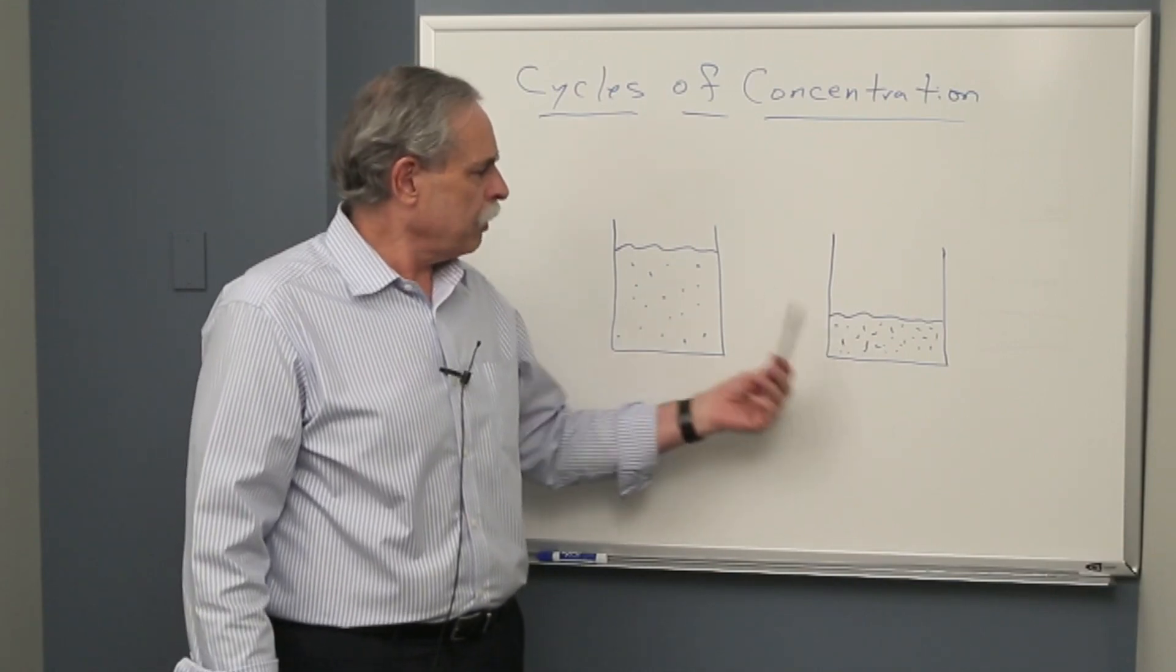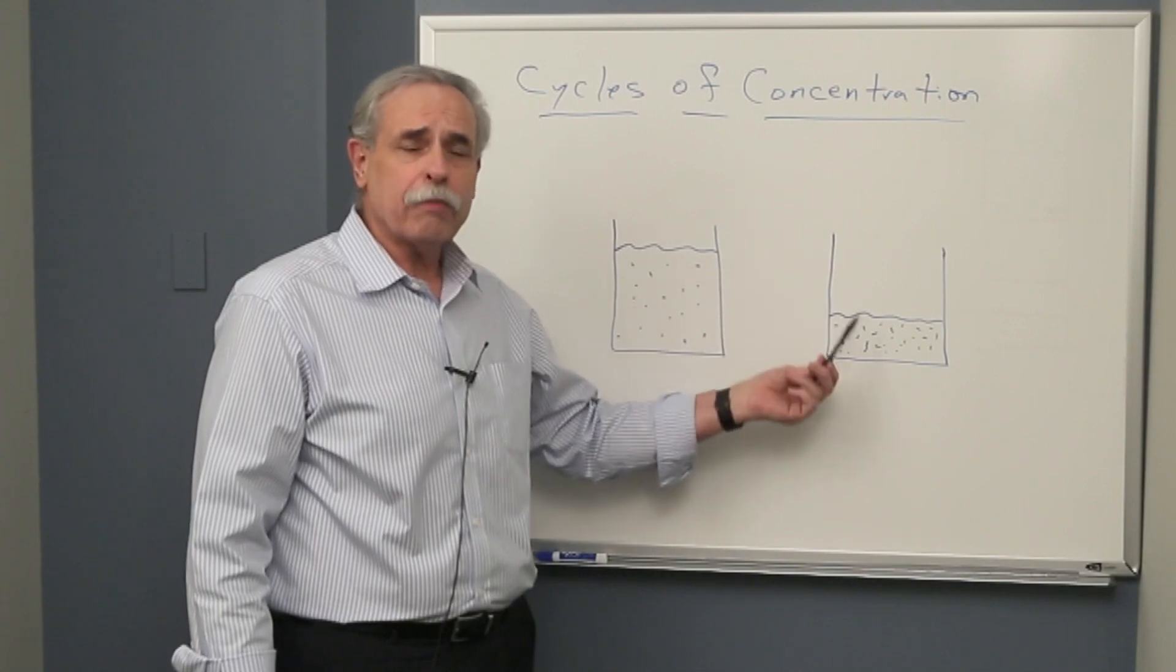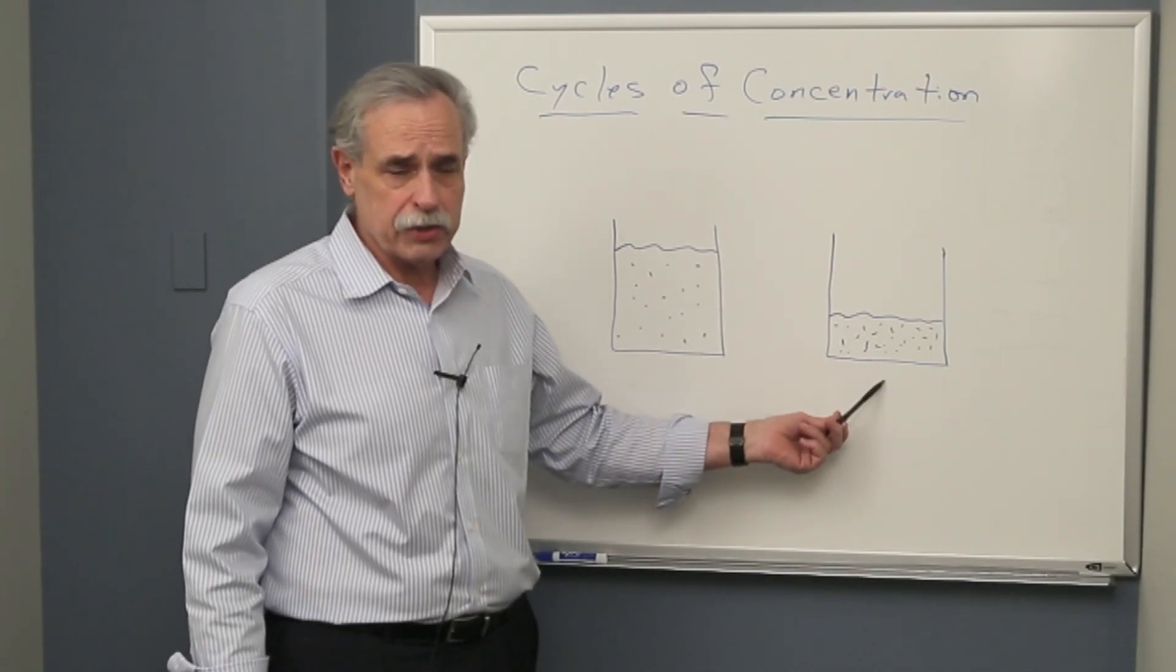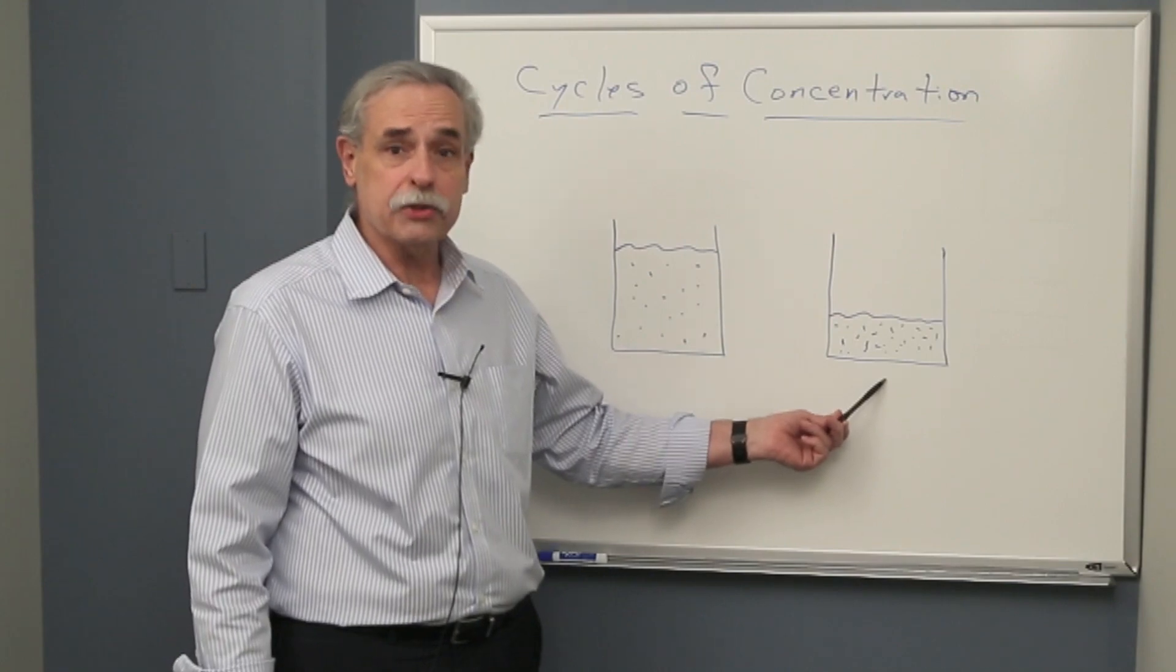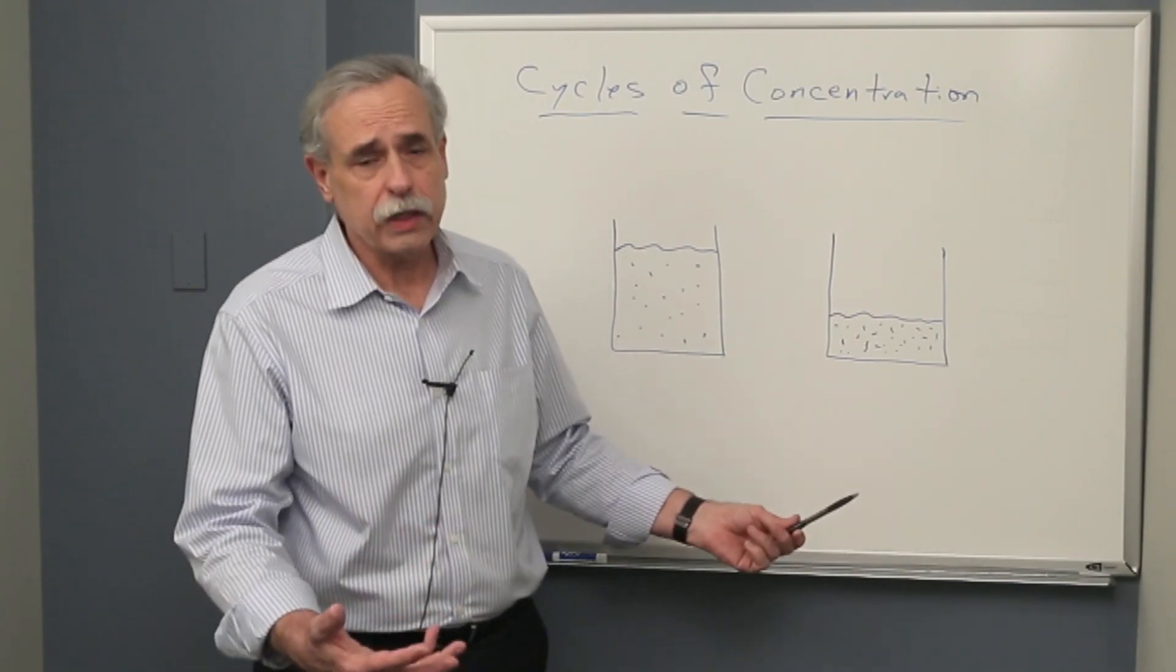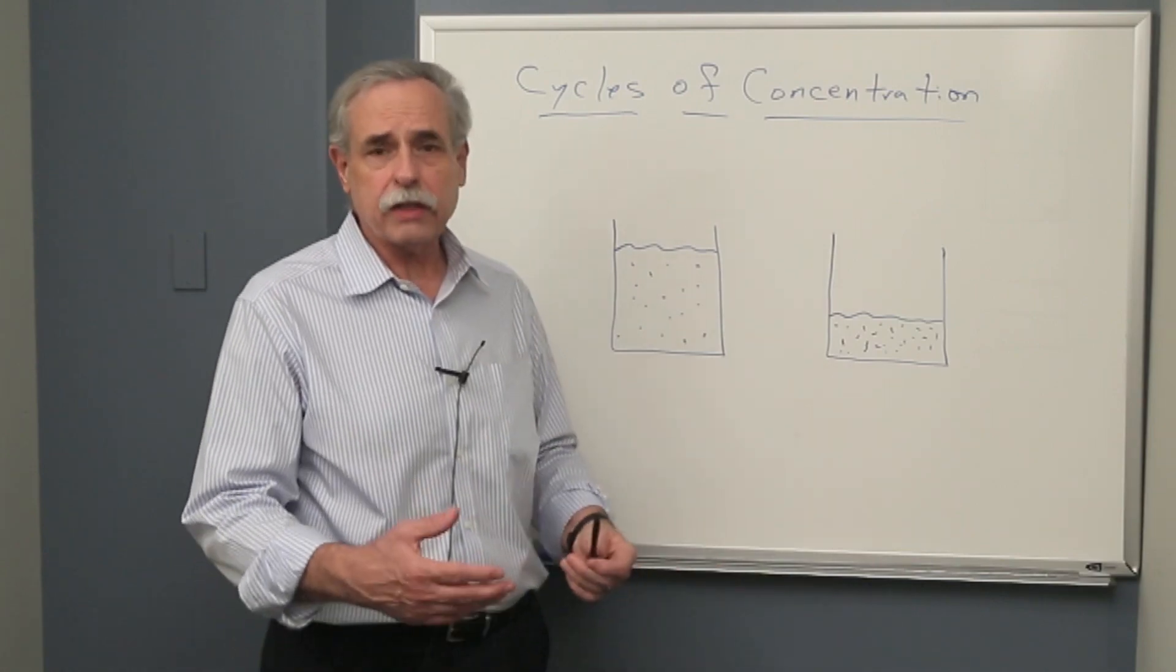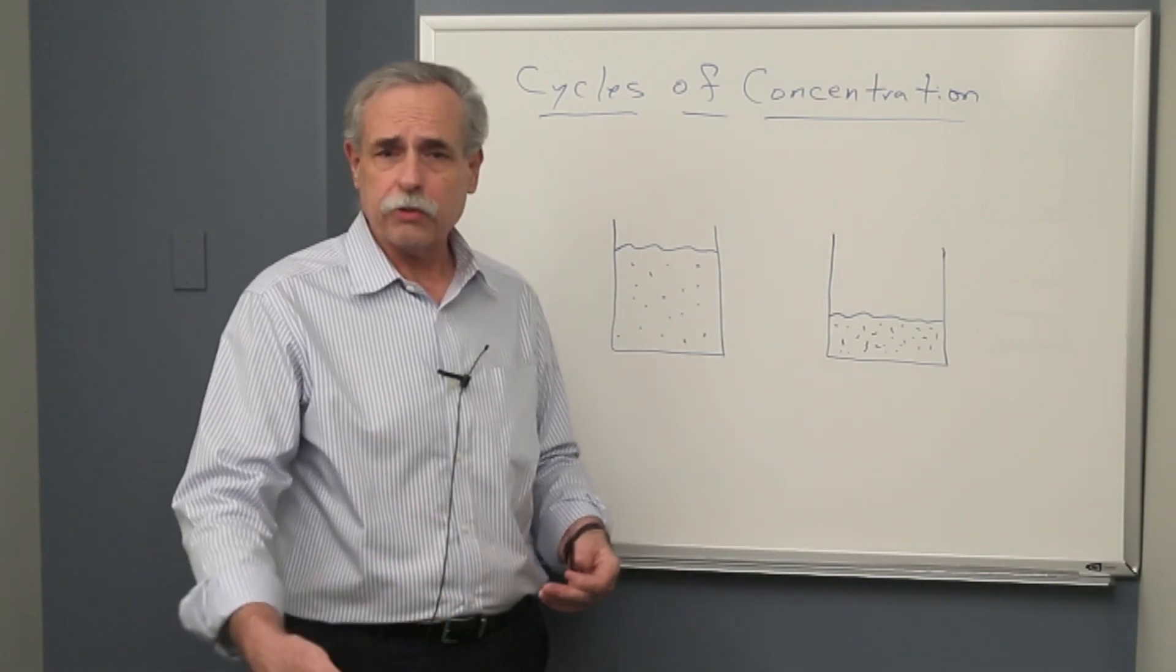So, for example, if you took the volume of water and evaporated half of it down, the concentration of solids that remains in the half of the volume is twice. So you have a cycle of concentration. Continuing evaporation beyond that, the cycles of concentration increased to two, three, and so on.